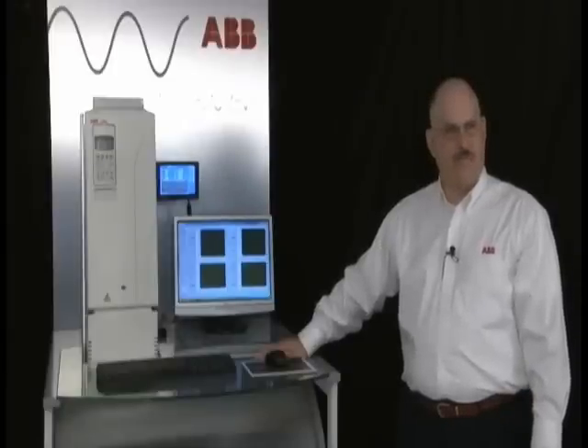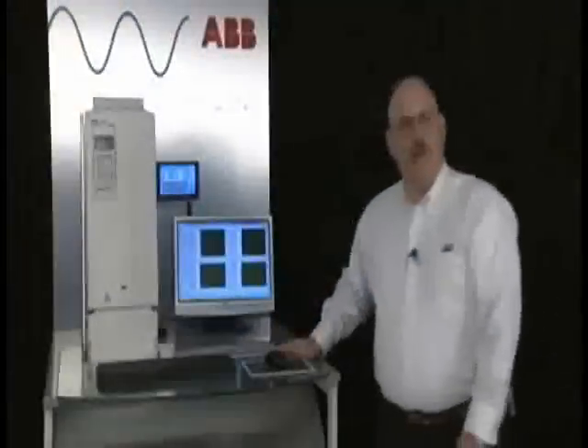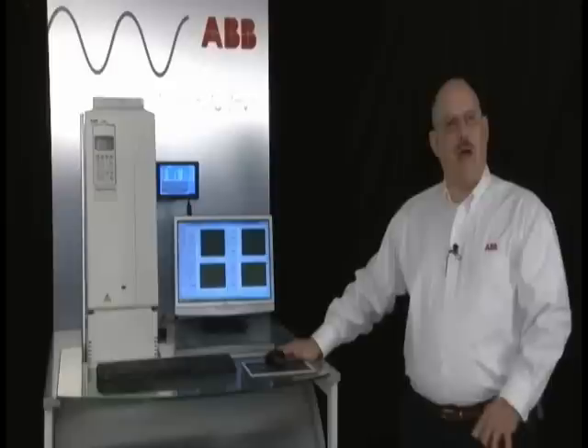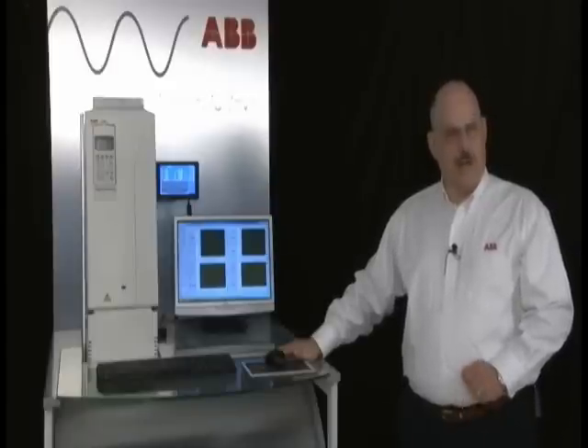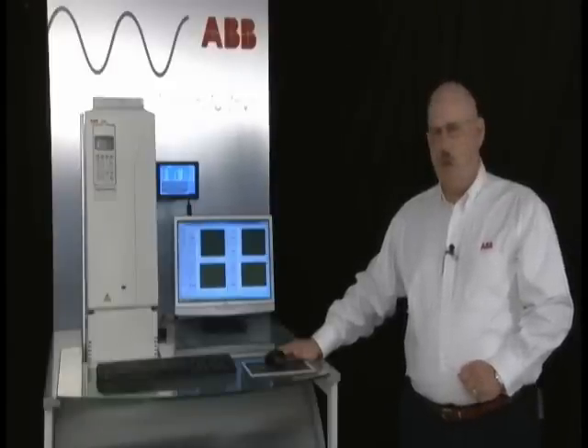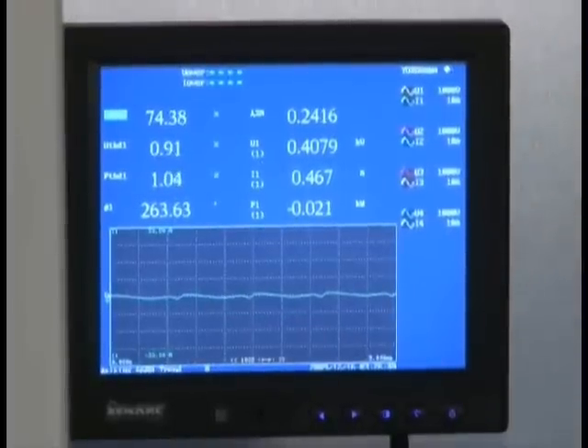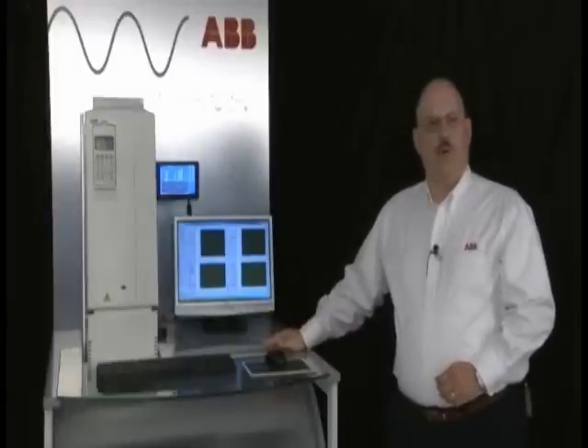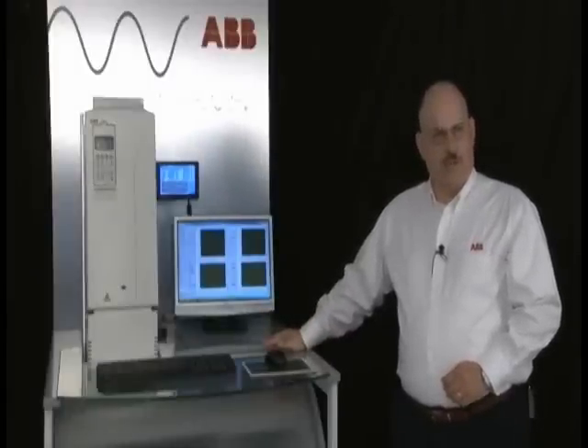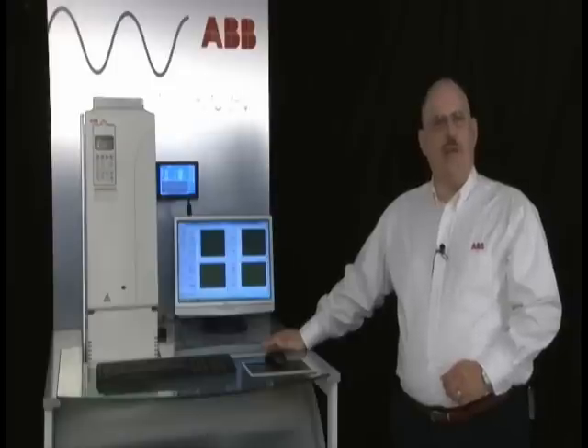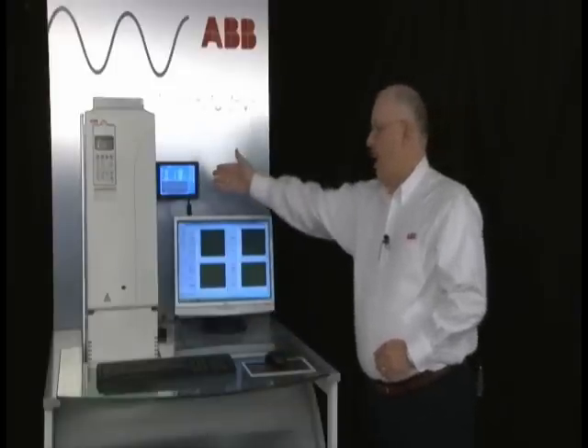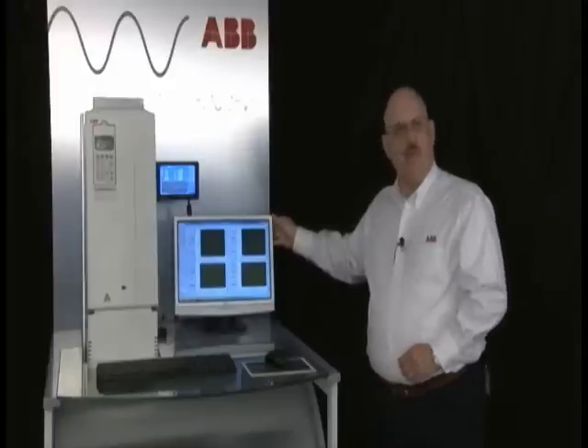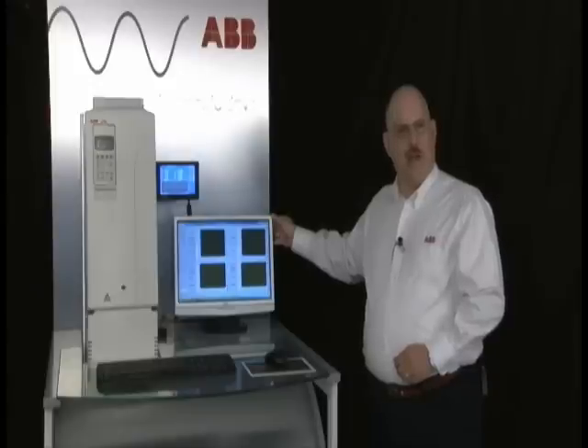We will be driving a fully loaded motor. The load is being provided by an additional DC drive in here so that we can operate under identical line conditions and identical load conditions. We have a harmonic analyzer with a display output brought up to the front of the demo unit so that we'll be doing actual harmonic analysis of both current distortion and voltage distortion. We'll have the ability to capture the output of the harmonic analyzer on this computer display, and we'll be able to compare side by side the results of the comparisons between 2 different technologies.